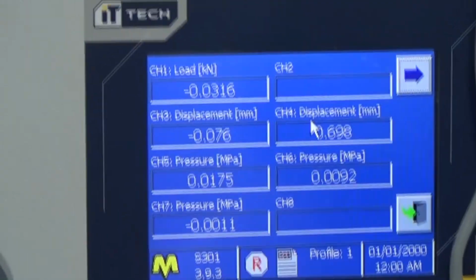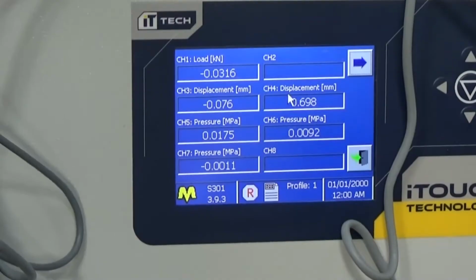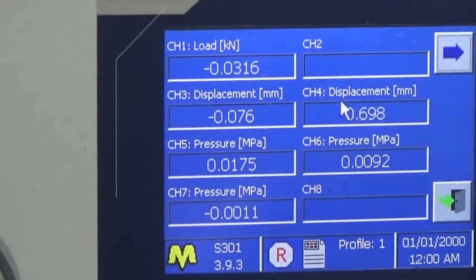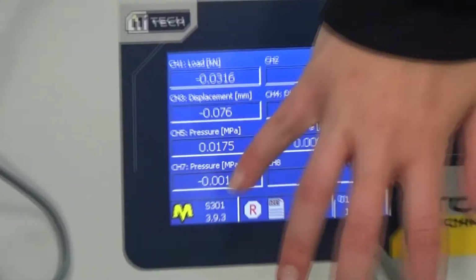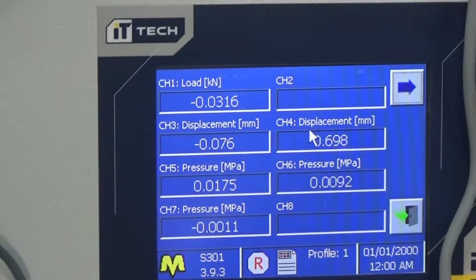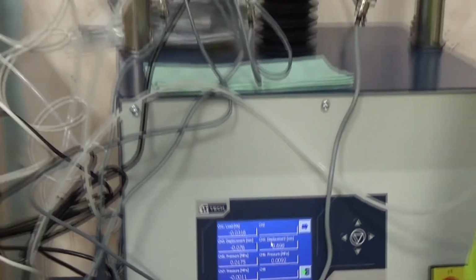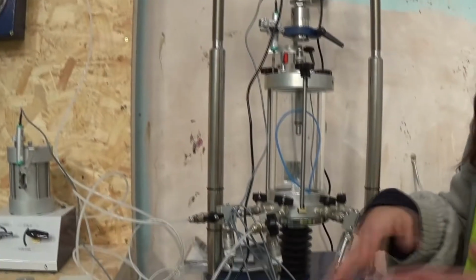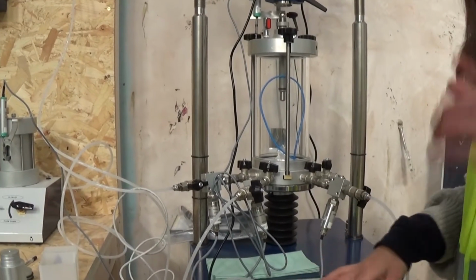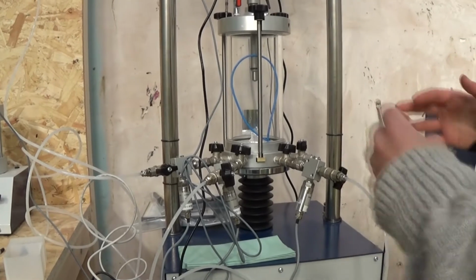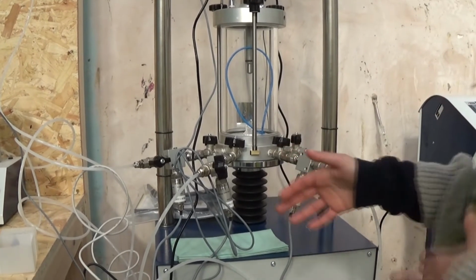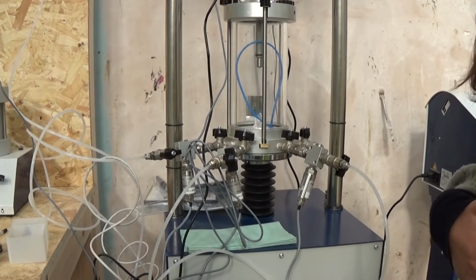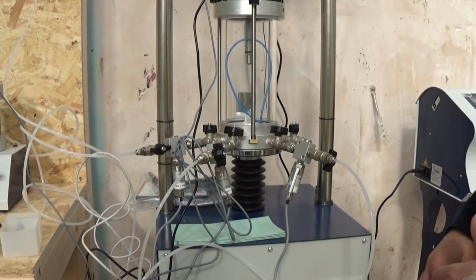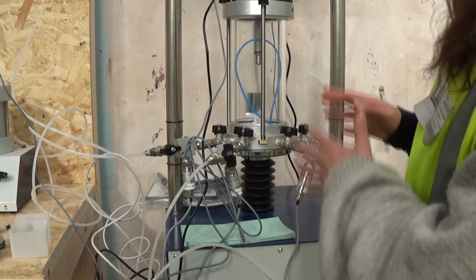For example, you will see the pressure increasing in the panel, and according to the right pressure transducer, you will see that also the pressure on the machine increases. It means that the pressure transducer and the panel are in line, are okay, are correct. If you see something different, you have to adjust the calibration of the pressure transducer. But in this case, the calibration is done.